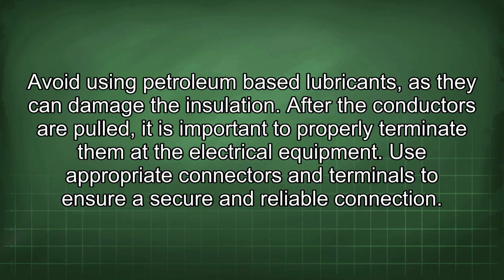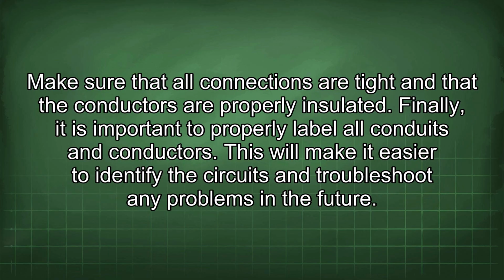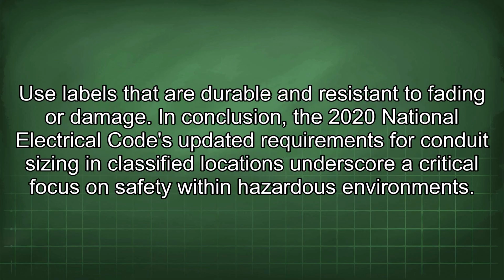After the conductors are pulled, it is important to properly terminate them at the electrical equipment. Use appropriate connectors and terminals to ensure a secure and reliable connection. Make sure that all connections are tight and that the conductors are properly insulated. Finally, it is important to properly label all conduits and conductors. This will make it easier to identify the circuits and troubleshoot any problems in the future. Use labels that are durable and resistant to fading or damage.